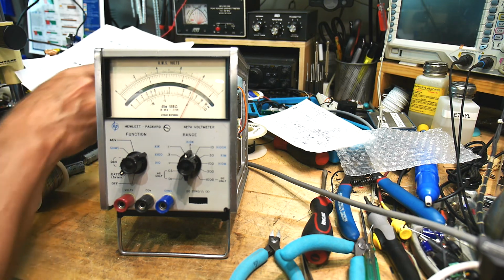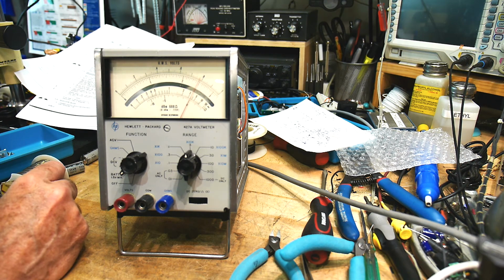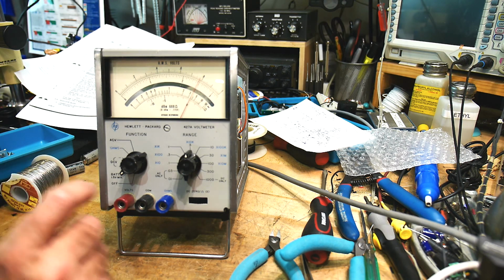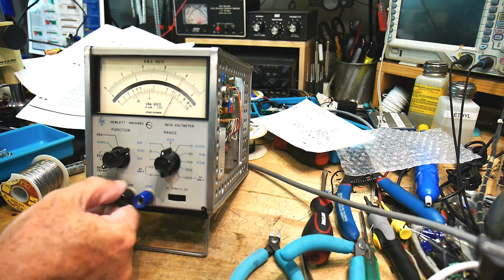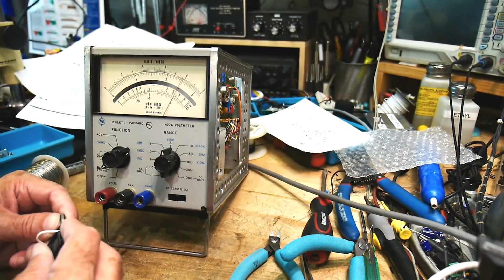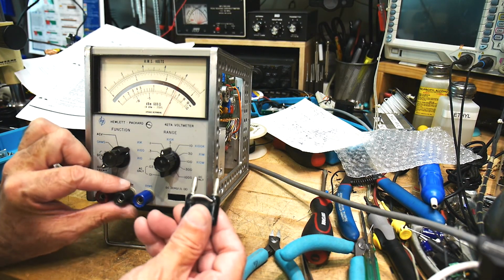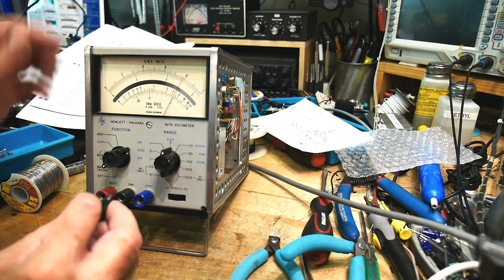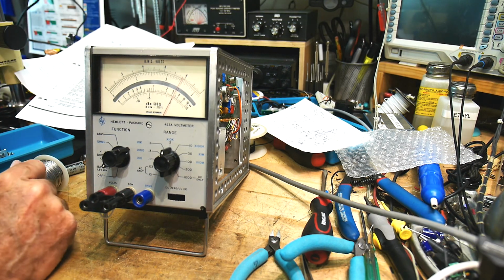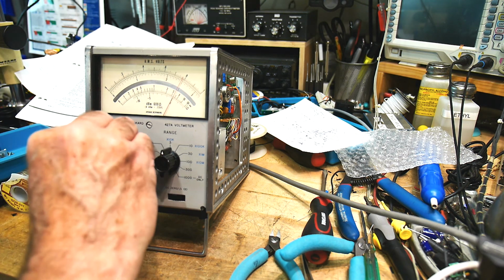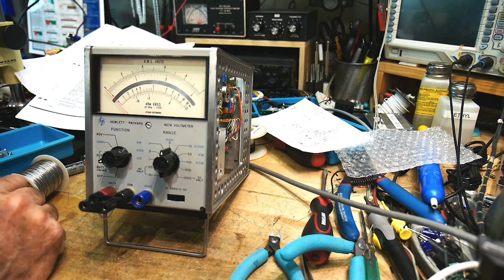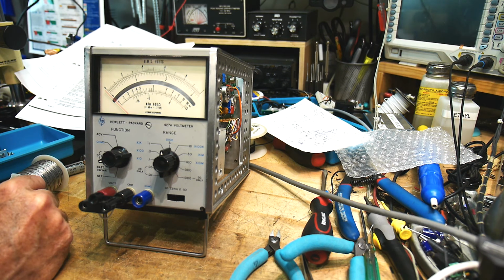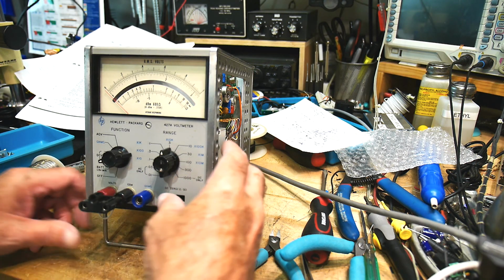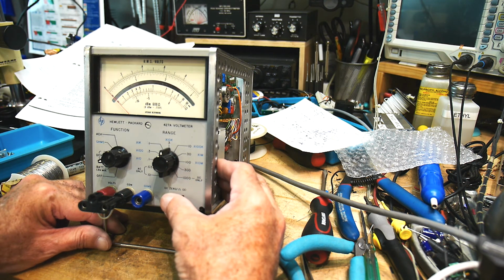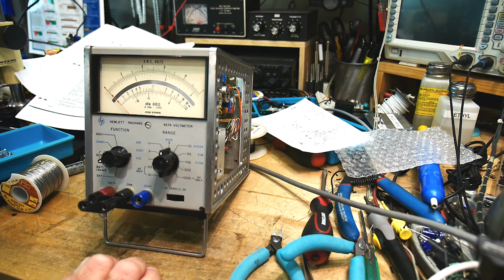And so, what does it say? Short the volts and COM terminals. Volts and COM terminals, short these together. I used to have a shorting block somewhere. Yeah, I do. I have a shorting block for calibrating other meters. So we will use that. So short these together. Set the function to AC, to DC plus or DC minus. So here's DC plus. Set the DC 0 for 0 deflection. Okay, that's this. So we're putting it right on 0.